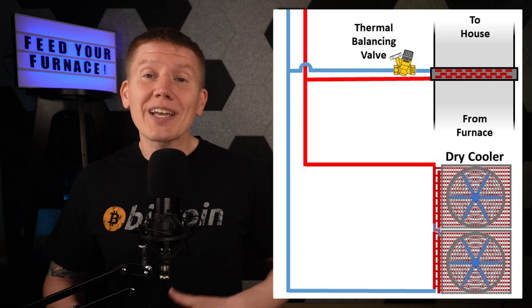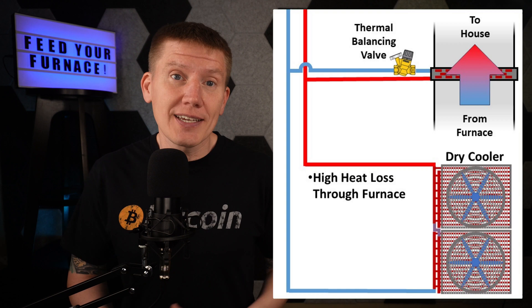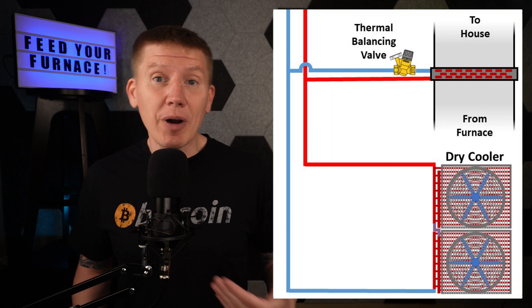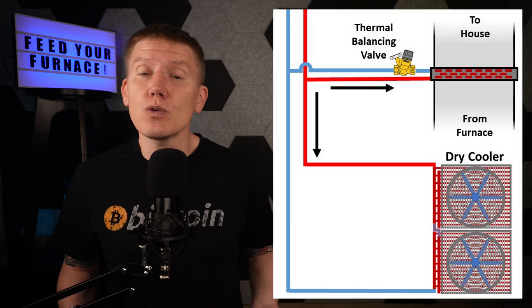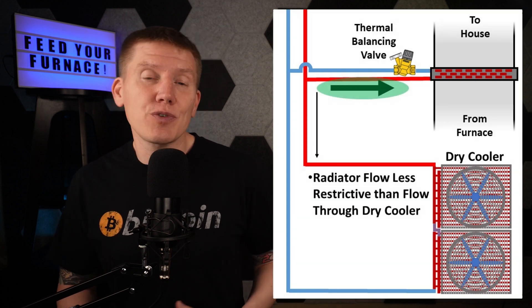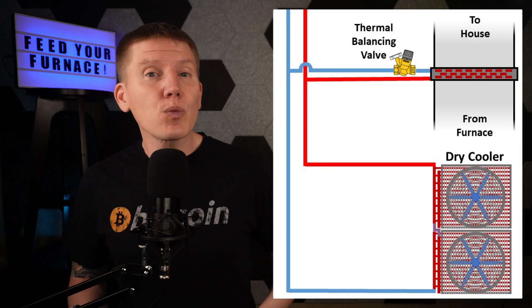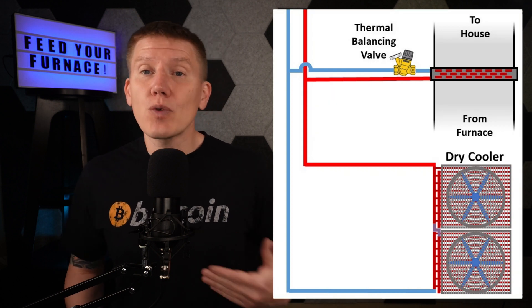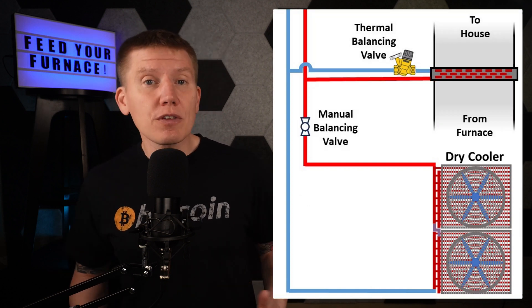If instead the radiator starts pulling a lot of heat from the fluid, the temperature at the thermostatic valve will decrease and the valve will open up, allowing more fluid to pass through the radiator. The limit to how much fluid can get to the radiator is going to be dependent on the relative flow restrictions between the two fluid paths. For this configuration to work, the flow path through the radiator must be less restrictive than the flow path through the dry cooler. The dry cooler will likely be further away, resulting in more fluid resistance. You could also make the piping to the radiator a lot bigger than the piping to the dry cooler, or you could add balancing valves to restrict the flow to the dry cooler.